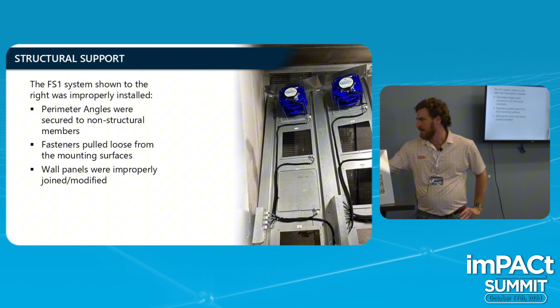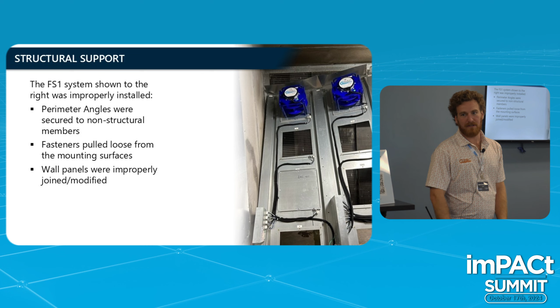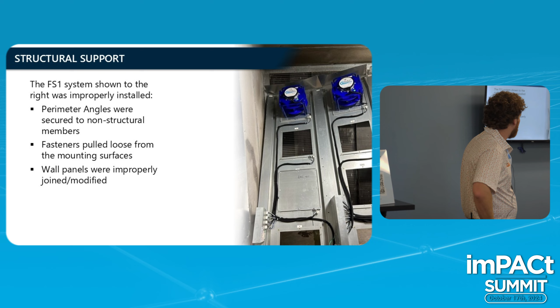Very rarely we had failures like that, and it usually just happens because someone isn't conscious of what they're actually securing the perimeter angle to. In this case, it was a perforated sheet metal liner inside the unit, really thin. They shot it into that, put it up, and turned it on, and shortly after it fell on the coil and screwed it up. It was a pretty big problem, so it's just another thing to be aware of.